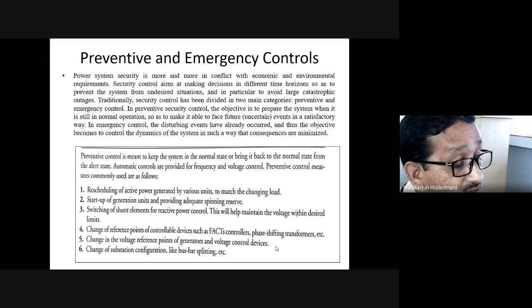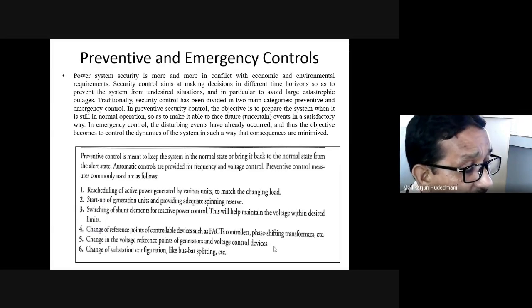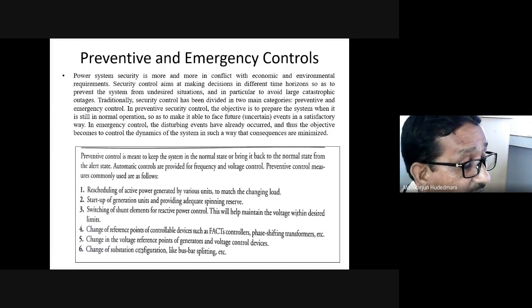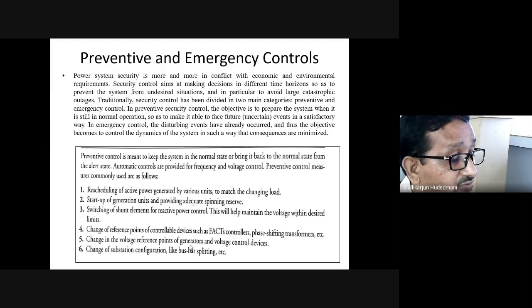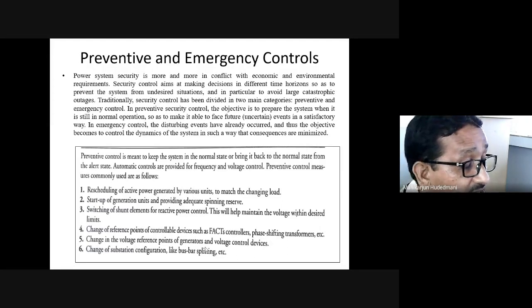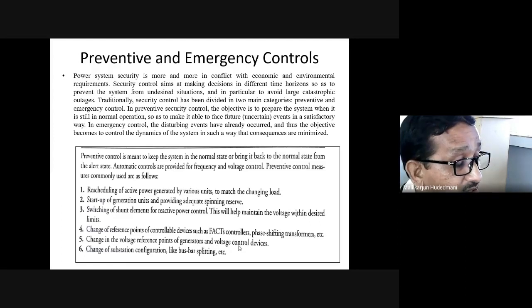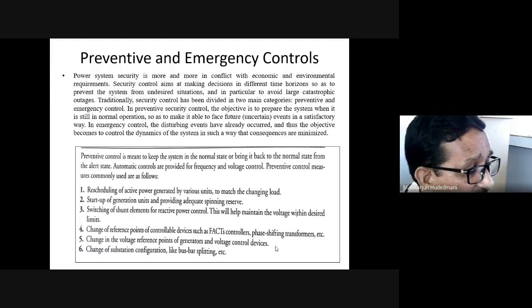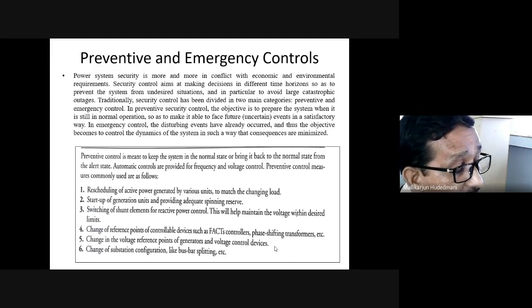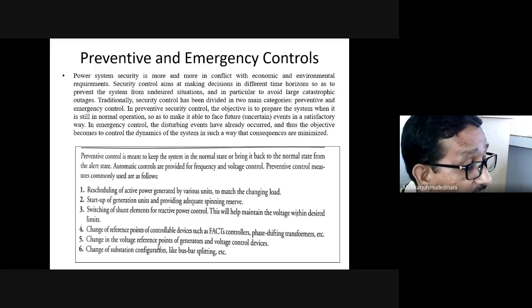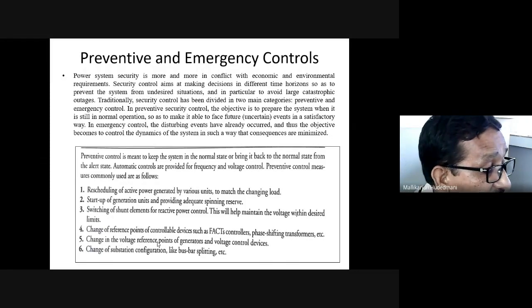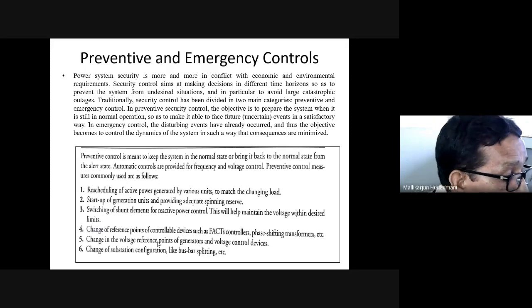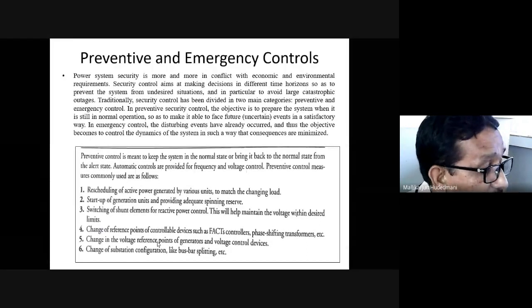Before really it is going to cause a tremendous effect, I as an operator can initiate these things to come into action so that such an impact will not arise. Prevention is already taken by this kind. Change in the voltage reference point of generator and voltage control device. This is an impedance issue, where we were saying generator is unable to boost its required voltage to a certain per unit voltage. Then make the set point change, excitation control or the particular generation input field I can control then and there only. It means to say change the voltage references.